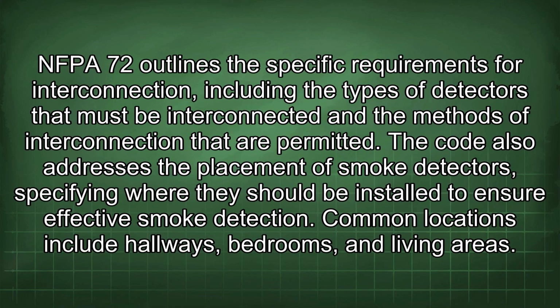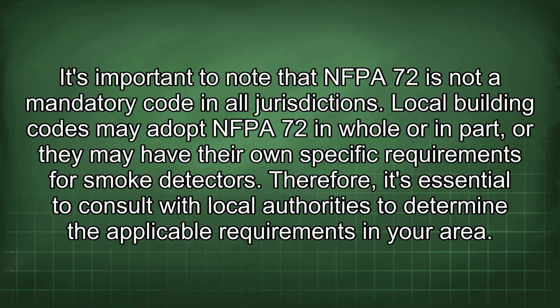NFPA 72 outlines the specific requirements for interconnection, including the types of detectors that must be interconnected and the methods of interconnection that are permitted. The code also addresses the placement of smoke detectors, specifying where they should be installed to ensure effective smoke detection. Common locations include hallways, bedrooms, and living areas. It's important to note that NFPA 72 is not a mandatory code in all jurisdictions. Local building codes may adopt NFPA 72 in whole or in part, or they may have their own specific requirements for smoke detectors. Therefore, it's essential to consult with local authorities to determine the applicable requirements in your area.